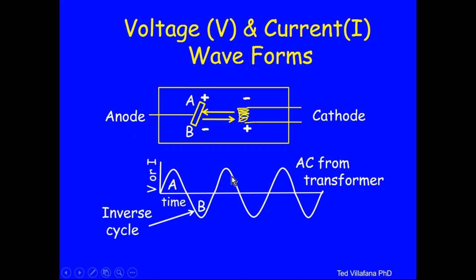Notice then that there'll be a tendency of the electrons to flow from the target to the filament. That's not supposed to happen. You don't want to bombard electrons up against the filament. The filament can't take that kind of beating. The filament is just a thin wire that cannot take that electron bombardment.